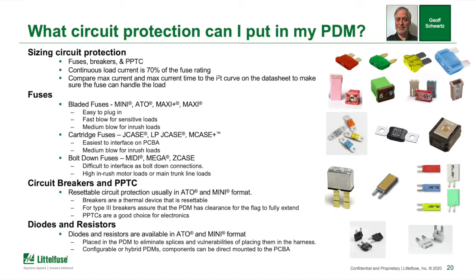PTCs are positive temperature coefficient devices. As they heat up from overcurrent, the resistance goes up, and they begin to stop the flow of current. They're good for electronics because there's no make-break, so you don't get spikes like you do with a fuse or circuit breaker. But they have a limited, relatively low range, max around 30 amps, whereas circuit breakers can go much higher.